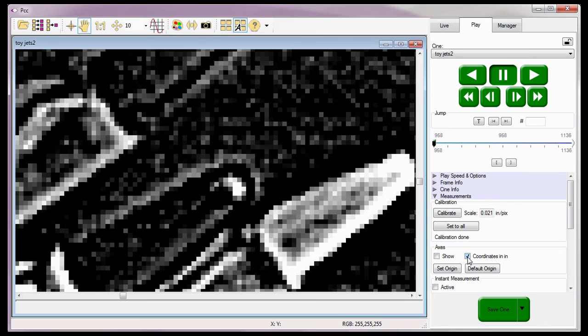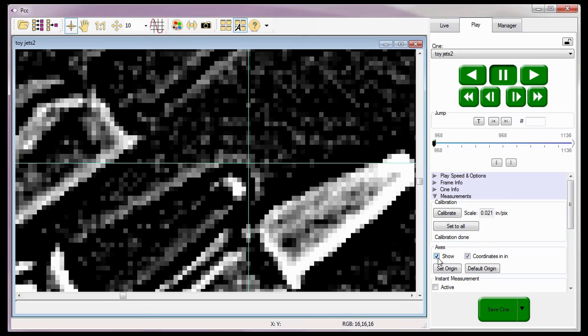Now that I can easily locate the tip of the jet, I can click the Set Origin button. But to select the point, I'll need to change the cursor back to the crosshair, then click the tip of the jet. To verify that the new origin point was set, I'll enable or check the Show option. Notice the crosshair now displays on the image — the point where the lines intersect is the origin, from which the coordinates will be calculated. If I move the cursor to the origin where the lines intersect, the software calculates the XY coordinates and reports them in the status bar as X0, Y0.